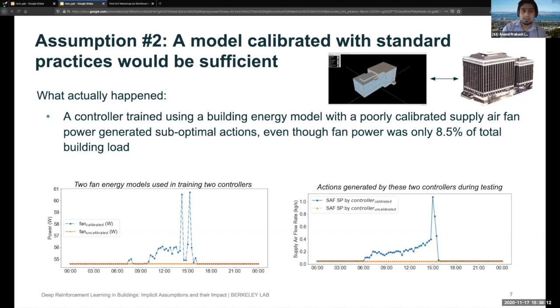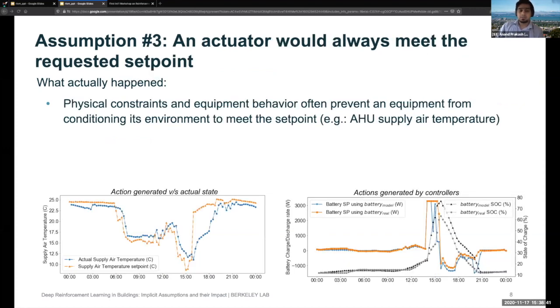It has to be noted that the supply air fan power is only 8.5% of the total building load. In spite of this small contribution, when the corresponding controllers were used to generate actions for the supply air flow rate in a building, as shown in the figure on the right, the controller trained with the uncalibrated fan does not actuate the supply fan at all, irrespective of the state of the building. This illustrates how inconsistencies between a simulated building and a real building can impact the performance of an algorithm.